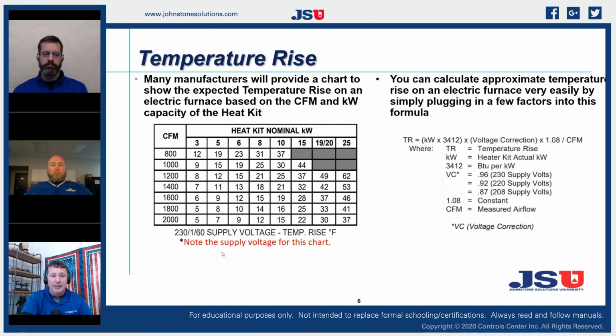So if I look at this particular one and I had approximately 230 volts AC, and I measured, let me grab my Sharpie here. If I had a 15 kW heater installed in this electric furnace, and I set all of my dip switches to run 1200 CFM, I could actually measure the performance of my blower simply by checking my temperature rise. My temperature rise should be 37 degrees on this thing. So if I go check my temperature rise and I find that I am running a 44 degree temperature rise on this system, but I had my blower set at 1200, now I need to go find out why. Why is my blower not moving the correct amount of airflow?